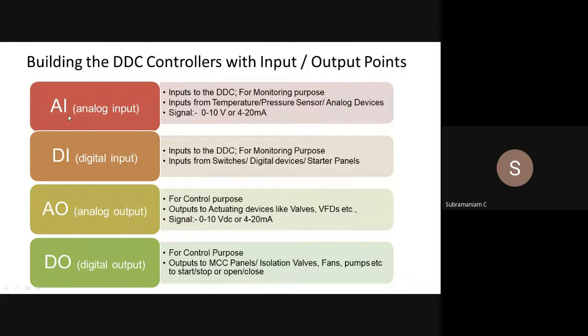instrument. And if it is connected to a controller, that is coming as an analog input. And if my switch, for example, the differential water pressure or air pressure differential pressure switch we talked about across a filter or fan, based on the fan low side and high side, there are some bellows there where it will go from NO contact to NC contact, which means I will have a digital input that will give in case that pressure builds from negative pressure to positive pressure of plus 1 inch or plus 2 inch or plus 3 inch static pressure.